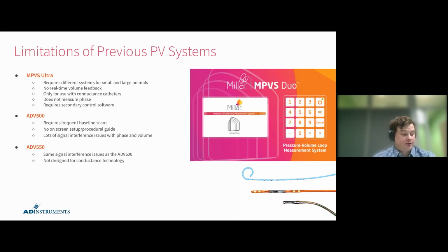Before I touch on all the great new things about the MPVS Duo, I just wanted to briefly go over some of the limitations of the older pressure volume systems that are out there. The old pressure volume system from Millar is called the MPVS Ultra. This system had a few limitations, the main ones being that it required different systems for small and large animals. There is no real-time volume feedback, so it's just a conductance measure until you calibrate it to give you a volume measure. It was only designed for use with conductance catheters. It did not measure phase, and it also required a secondary control software to be run on your computer.